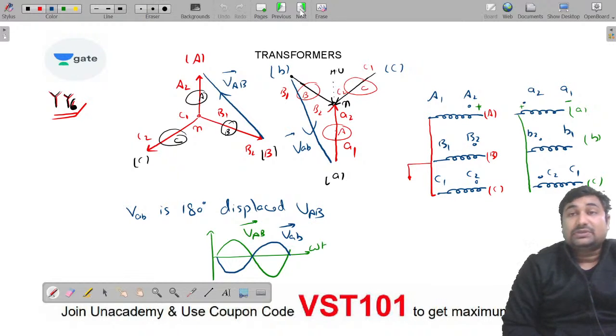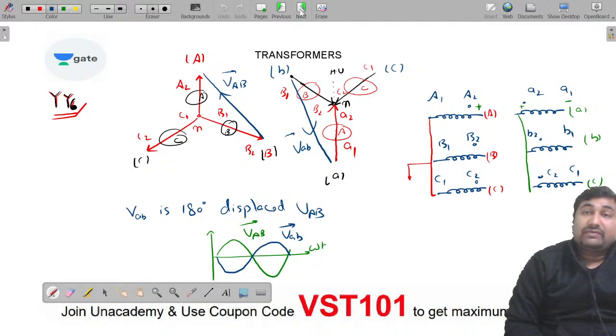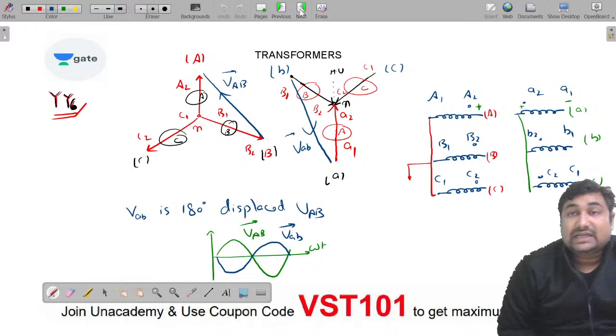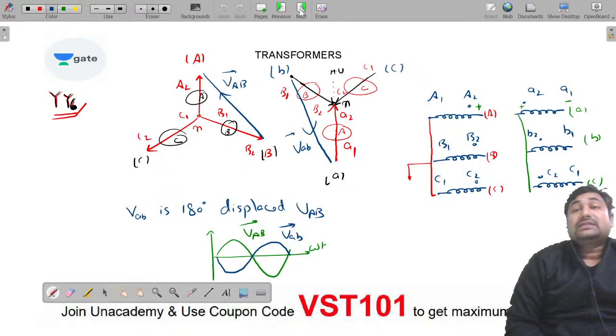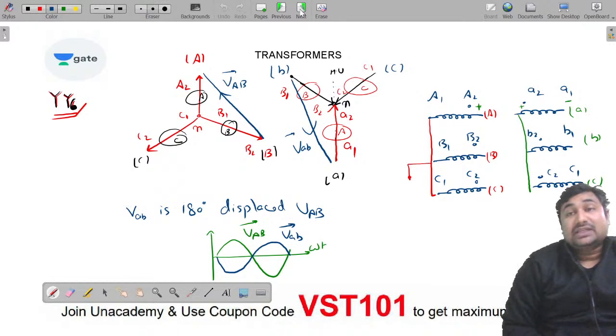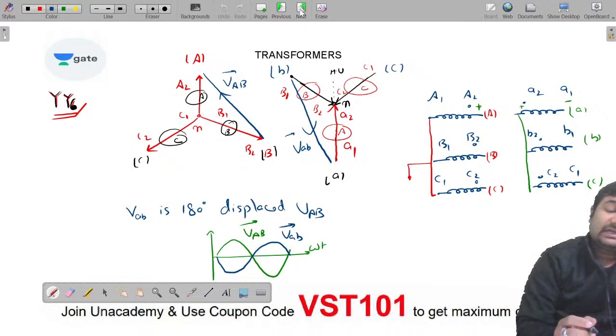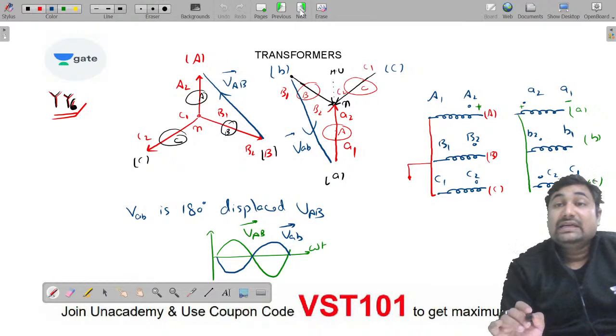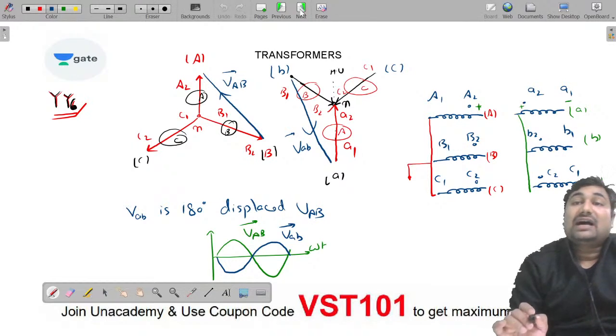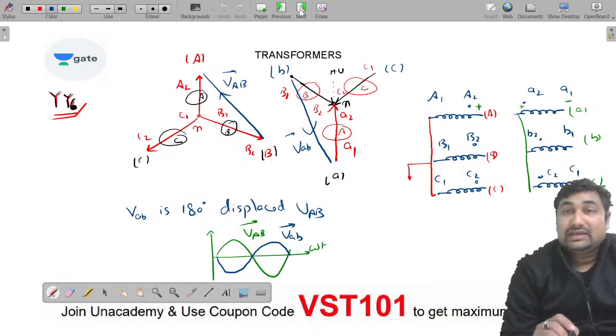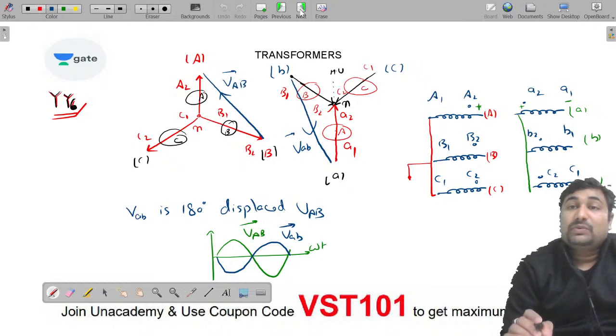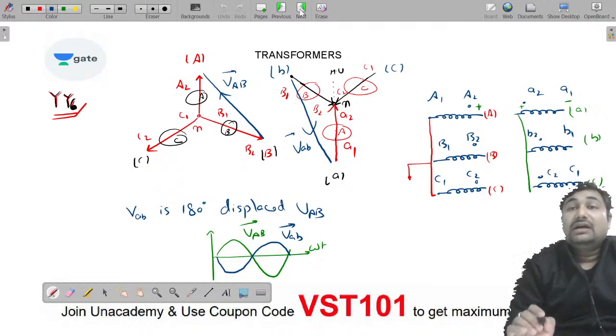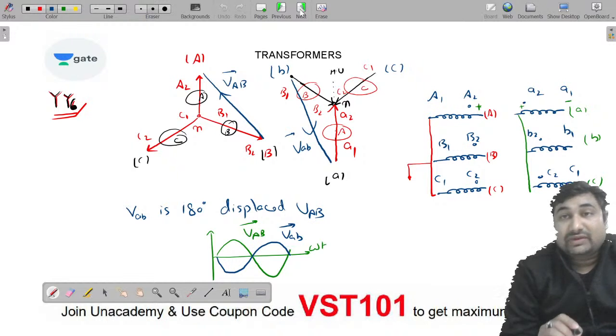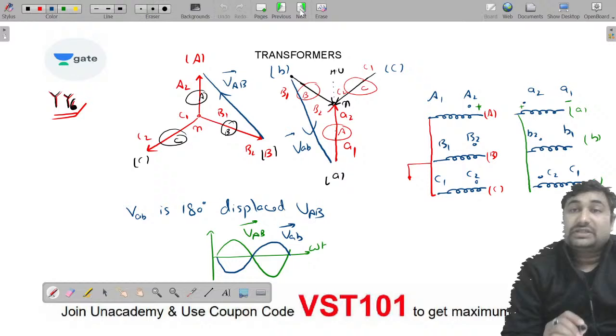If we talk about saturation and hysteresis, then to get sinusoidal induced EMF, which is the main desire for any transformer, flux must be sinusoidal, and for that current must be non-sinusoidal and peaky in nature, containing an enhanced third harmonic component. But third harmonic current is not allowed to flow in the transmission line, because it creates objectionable communication interference.